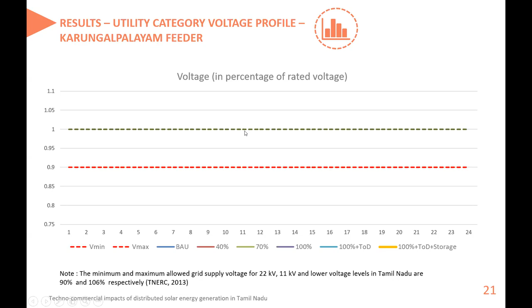Now we will see the utility category voltage profile for a single day for Karungalpalayam feeder, which is the worst affected feeder. Please note the minimum and maximum allowed grid supply voltage: according to TNERC, it can go up to 10% below the rated value, and 6% above the rated value. I have shown the limit in red color. Let us see what we have observed for the BAU scenario. Here you can see that for most of the hours, Karungalpalayam feeder is violating the acceptable limit.